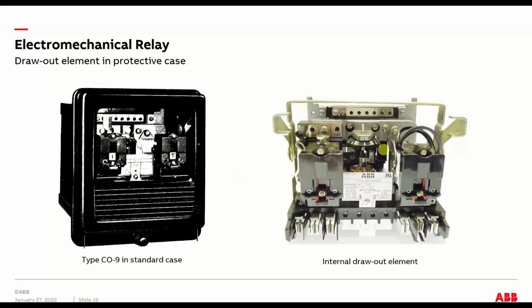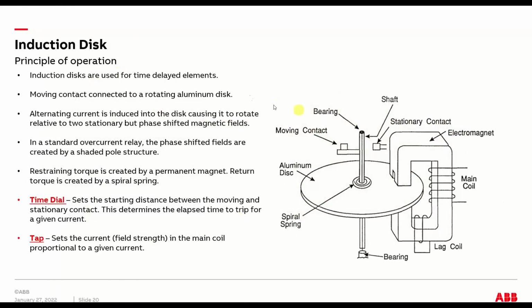Here's a nice slide just showing you the internal component. This is the actual relay itself that's been drawn out of the box. This is kind of a bad picture, but you can see this is an overcurrent relay, and I'll get into some more of the details, but this is the internal of that. Basically, the overcurrent relay uses an induction disk to time itself for the time overcurrent portion of the protection. And there's two basic settings for an induction disk time overcurrent. There's the time dial, which sets the delay, and there's the tap, which sets the pickup. That's it. Now you get into your multifunction relays and things start to get really complicated, but if you go back to the basics, two settings: time dial, tap.